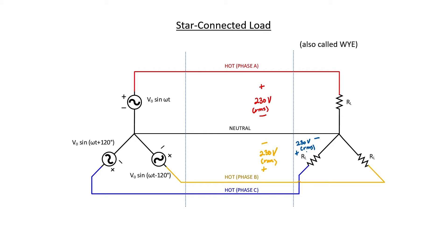If the load is balanced, there won't be any current flowing back through the neutral. If the load is unbalanced, then current will flow through the neutral. This explains why in residential areas, you have to have neutrals because there's no guarantee that the loads are going to be perfectly balanced. Now, over a very large geographical area, well, then yes, you can start counting on loads to be balanced.